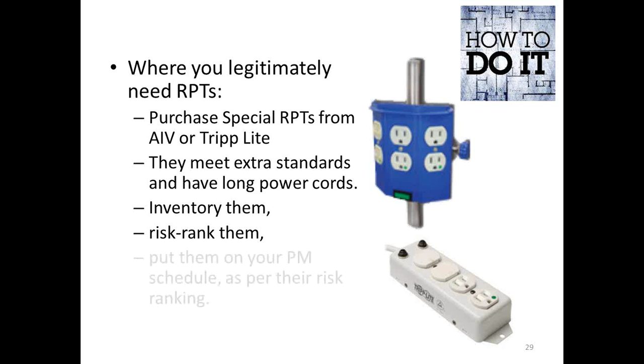Extra steps for these special RPTs: once you plug in all the pieces of equipment you intend to use, you have to make sure the item does not draw more than 75 or 80 percent, I've seen conflicting numbers, of the amperage capability of the RPT. So look at the circuit breaker. If it's 15 amps, you need to measure the current draw of everything plugged in and make sure it's not over 80 percent of that.